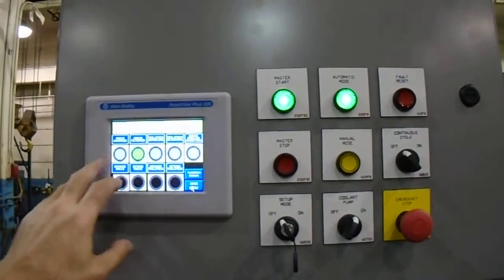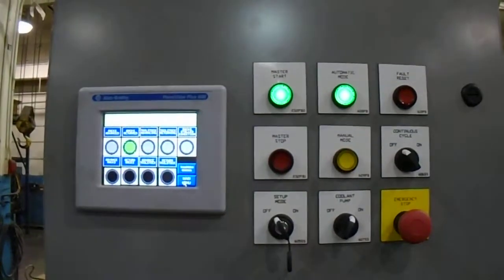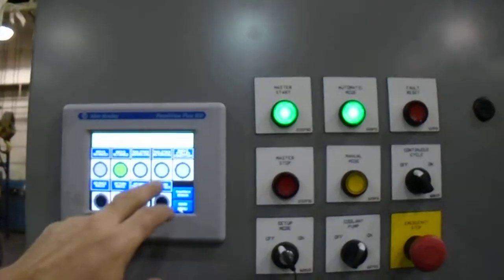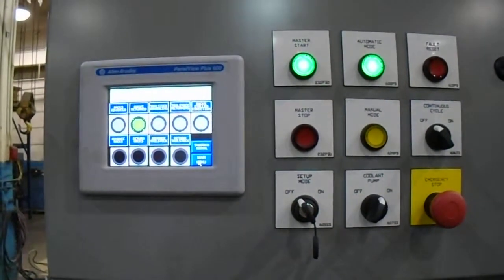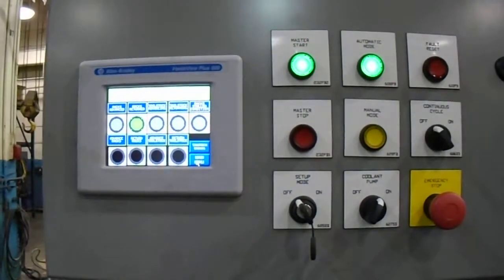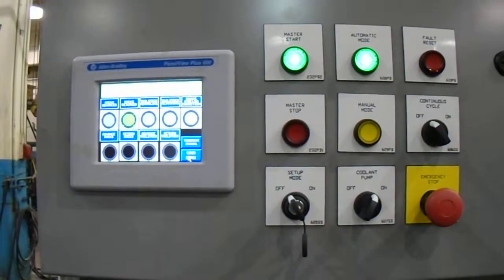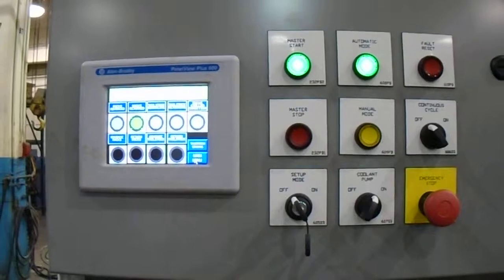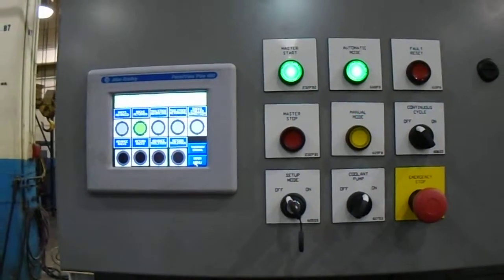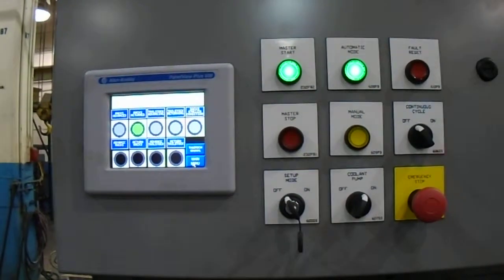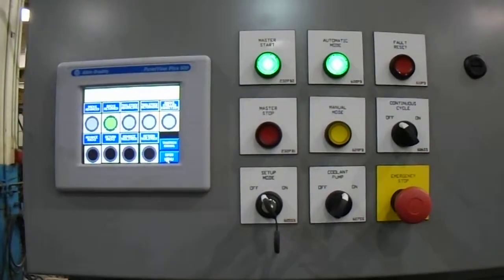The manual screens, you have a manual screen with advance racks and return racks, tailstock advance or tailstock return. There's a sequential condition of how you can do that. First, you have to have the headstock at load position, then you can advance the tailstock in. Once it sees part present, then you can advance the racks, then you return the tailstock, then you return the headstock to clear, then you can return the racks. That's a manual cycle.